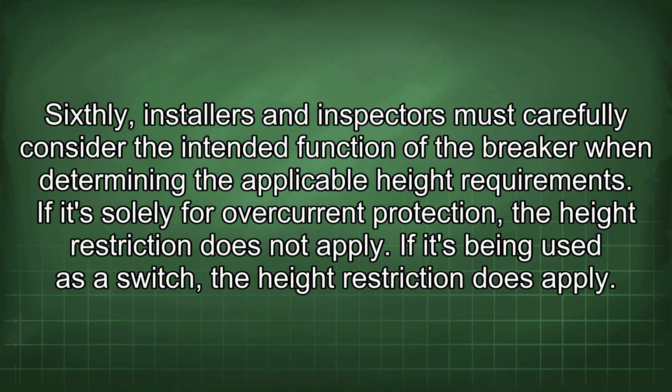Sixthly, installers and inspectors must carefully consider the intended function of the breaker when determining the applicable height requirements. If it's solely for overcurrent protection, the height restriction does not apply. If it's being used as a switch, the height restriction does apply.